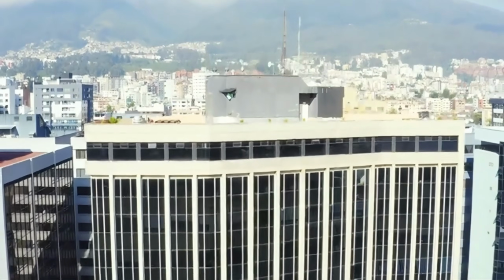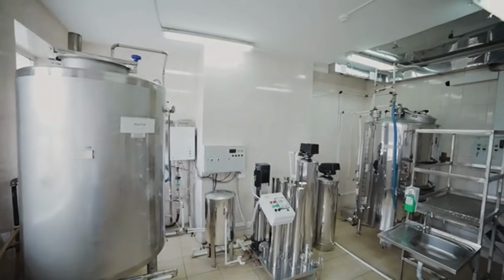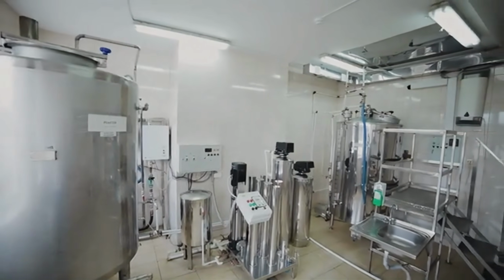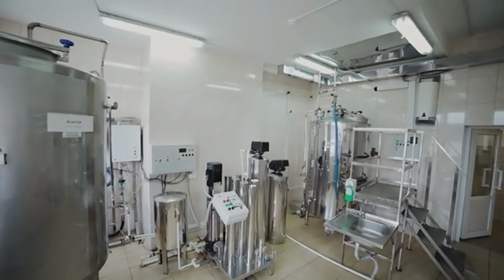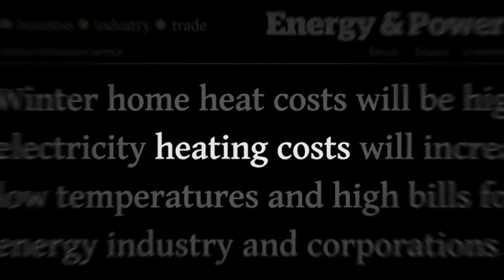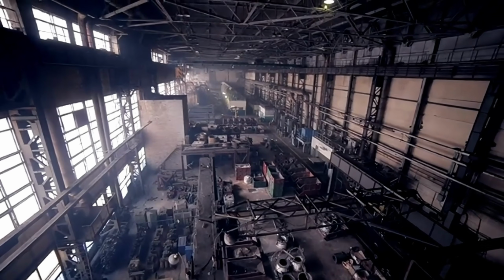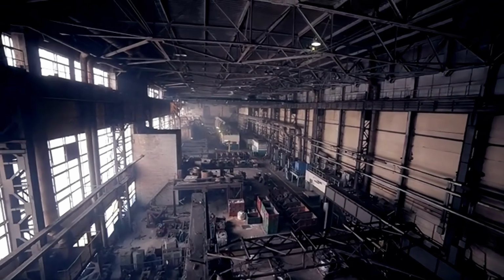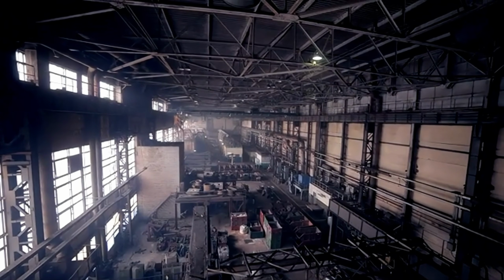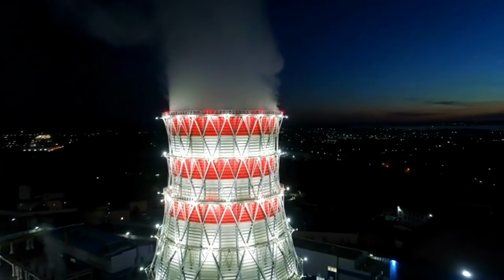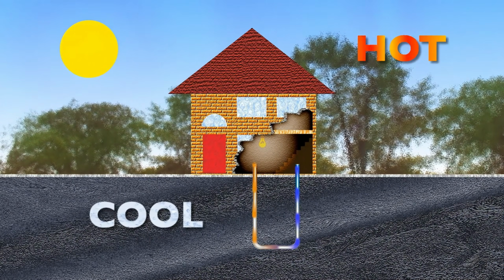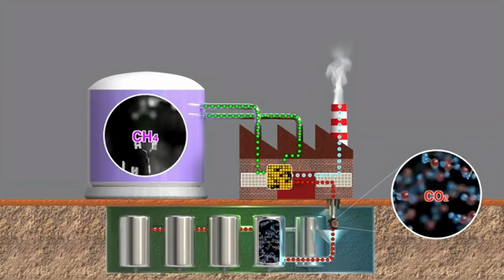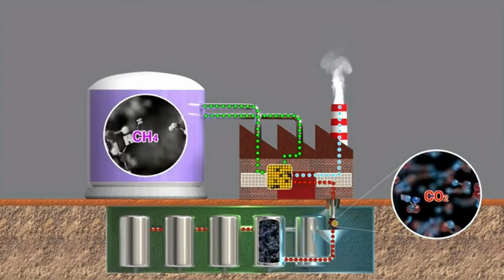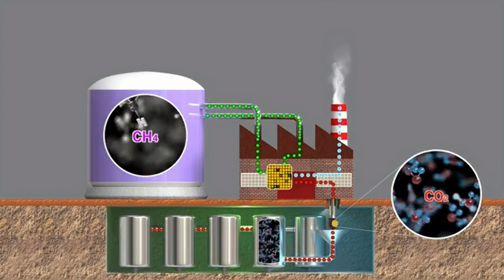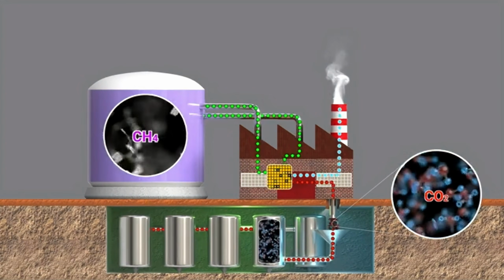Then the commercial scale, which is where the real money is. Large buildings across the country are cooled by lithium bromide absorption chillers in hospitals, universities, industrial plants, and district energy systems. The logic there is purely economic. Those facilities already produce enormous quantities of heat, whether from steam plants, from industrial processes, or from generators producing electricity on site. That waste heat used to go up a cooling tower and vanish. Feed it to an absorption chiller instead, and it produces air conditioning for effectively nothing from energy that was already being thrown away. Engineers call the combined arrangement trigeneration, meaning one fuel input producing electricity, heating, and cooling together, and it is standard practice in serious facility engineering.